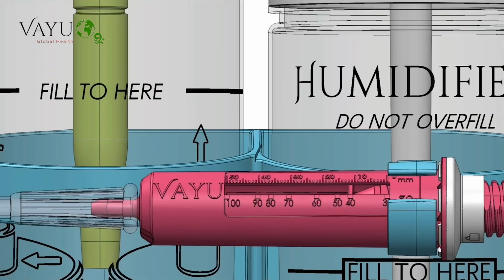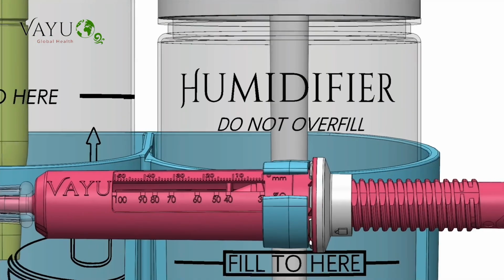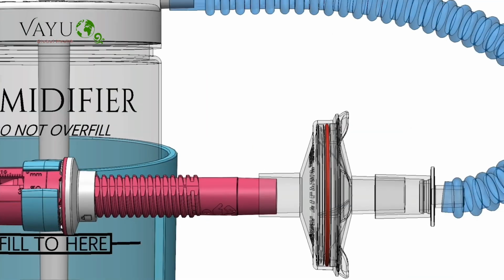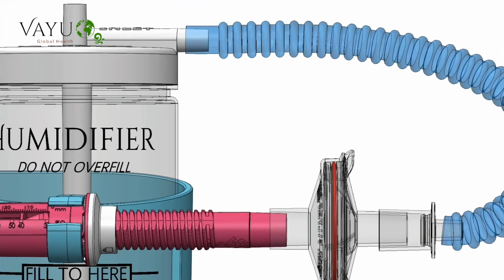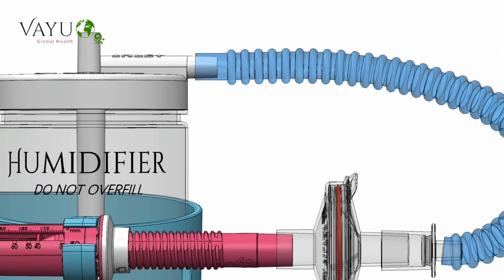The blender innovatively blends pure oxygen to an adjustable concentration with atmospheric air by the Venturi effect. This ensures the patient does not become hyperoxic and helps prevent consequences such as bronchopulmonary dysplasia and retinopathy of prematurity. The blended air is then filtered using a reusable filter, which removes viruses and other pathogens. The gases are then humidified in a bubble humidifier to prevent the patient's airways from drying out.